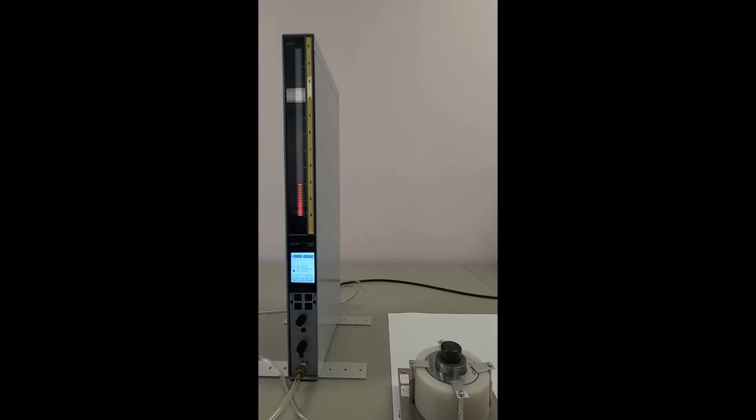Hi folks, today we're going to look in this video at the TIR operation of the L9100 Air Column gauge. TIR stands for Total Indicating Readout. When the TIR is on, you'll see it will say up in the upper right corner of the display here, TIR in red letters. The idea here with TIR is it allows for dynamic readings while a part is being moved or rotated in a fixture.